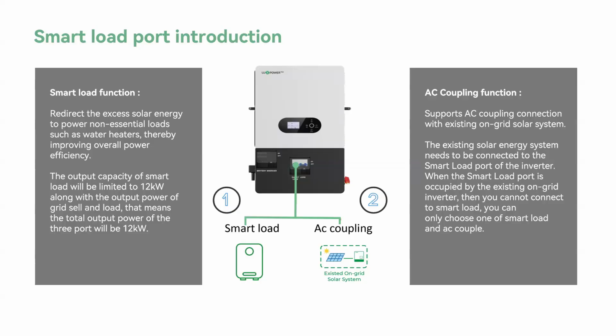As for the AC coupling function, we support AC coupling connection with existing on-grid solar systems, and the existing solar system needs to be connected to the smart load port instead of the GEN port like the other models. When the smart load port is occupied by the existing on-grid inverters, we cannot use the smart load function anymore. So we have to choose either smart load or AC coupling function.